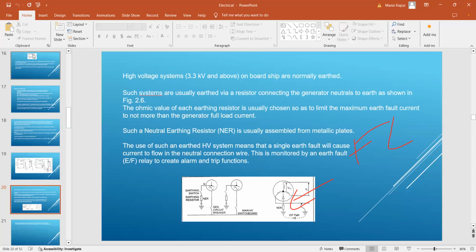Such a neutral earthing resistor is usually assembled from metallic plates. The use of such an earthed high voltage system means that a single earth fault will cause current to flow in the neutral connection wire, and this is monitored by an earth fault relay, which is going to give an alarm and trip your generator.